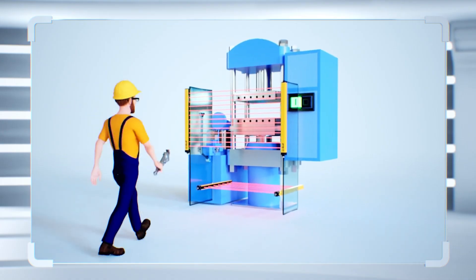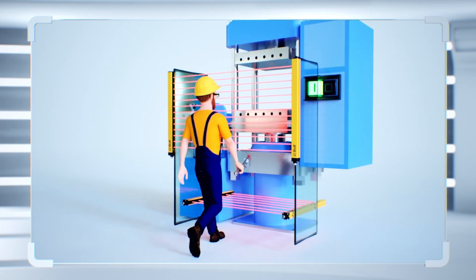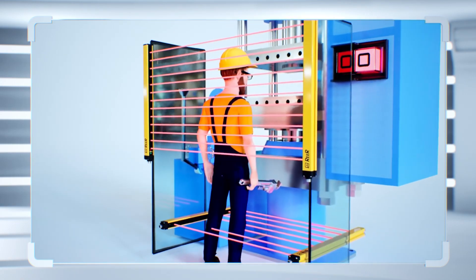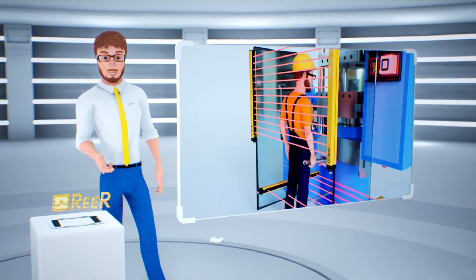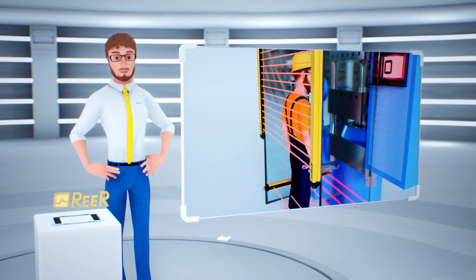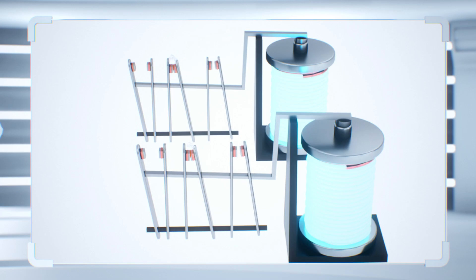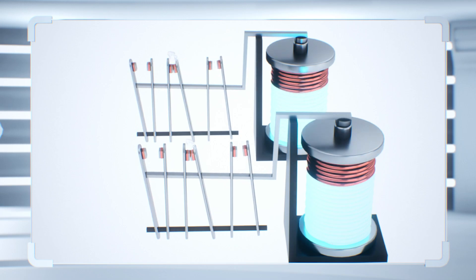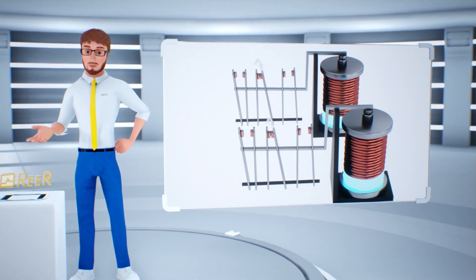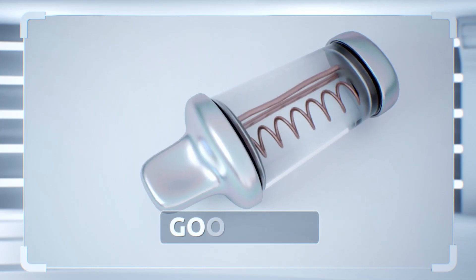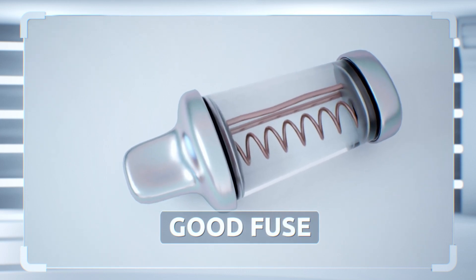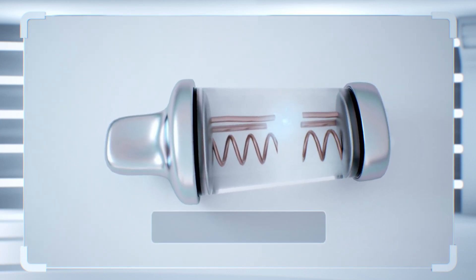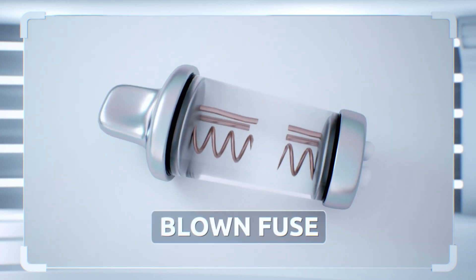The machine designer must take this type of failure into consideration and exclude it at design stage. For example, an over current flowing into both relays' contacts could weld both of them. In this case, we must protect the relays with a fuse that will blow, interrupting the current, before the relay contacts weld.